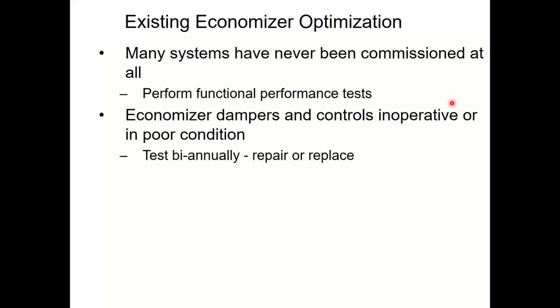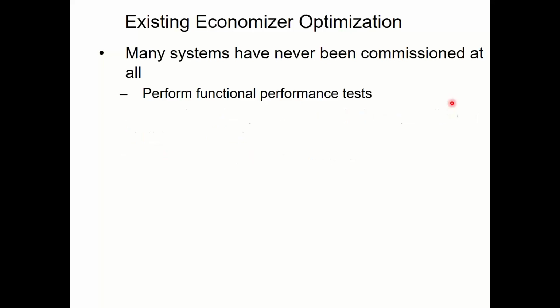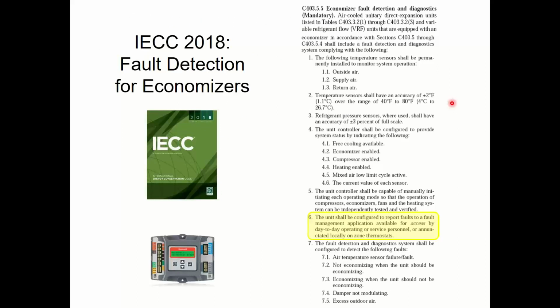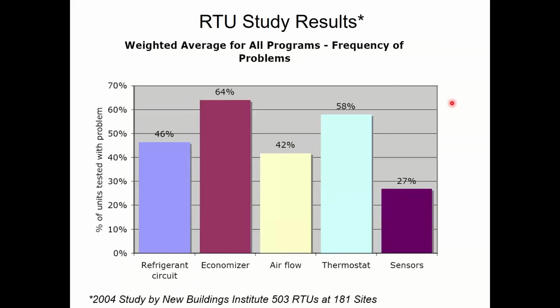And if it breaks, no one's going to know. No one knows. Because the compressor just turns on. I call for economizer, damper didn't open because it's broke. Well, after a little while, I call for second stage cooling and the compressor turns on. And nobody knows. Right? So that's why we have to have this alarm on here, because it's a problem in the background that wastes a bunch of energy and nobody knows it's happening. And it happens a lot, right?